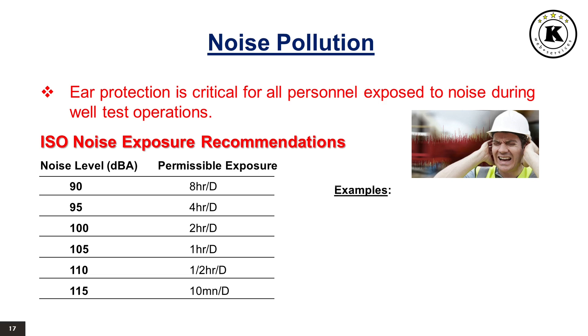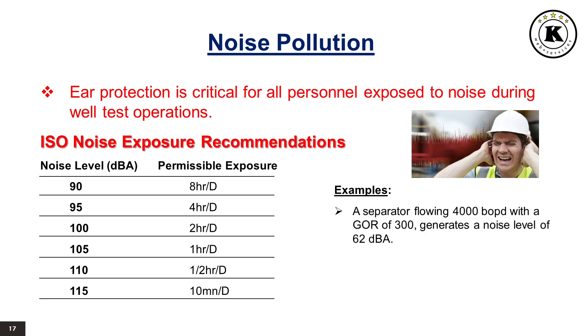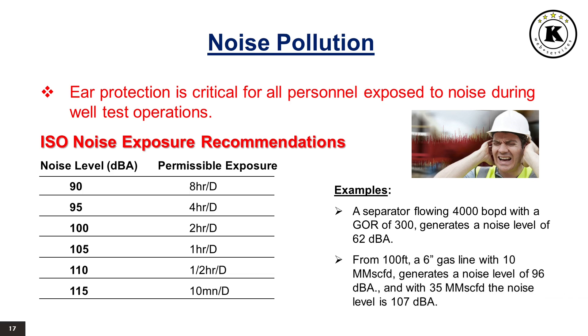For example: a separator flowing 4,000 barrels of oil per day with a GOR of 300 generates a noise level of 62 decibels. From 100 feet, a 6-inch gas line with 10 million standard cubic feet per day generates 96 decibels, and with 35 million standard cubic feet per day the noise level is 107 decibels.